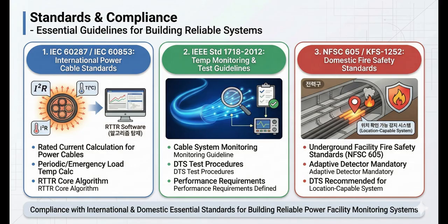Cable ampacity and thermal modeling follow IEC standards, and performance requirements and test procedures for temperature monitoring systems can reference IEEE guidelines. In Korea, fire safety trends increasingly emphasize detection systems that can identify exact locations. In short, DTS gains trust in the field when it is designed as a full package, aligned with standards and regulations, not just as a standalone technology.